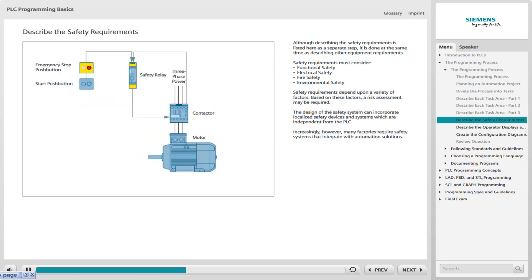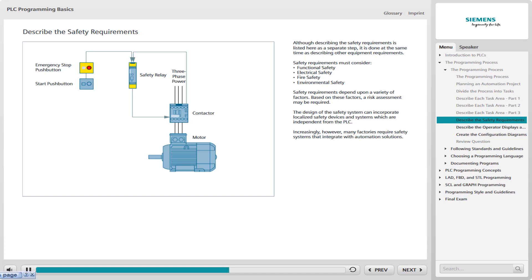The design of a safety system can incorporate localized safety devices and systems which are independent from the PLC. For example, the accompanying graphic shows an emergency stop, e-stop, push button wired to a safety relay. When the e-stop push button is pressed, the safety relay de-energizes the contactor that provides power to the motor, and the contactor signals the safety relay when its contacts have opened.